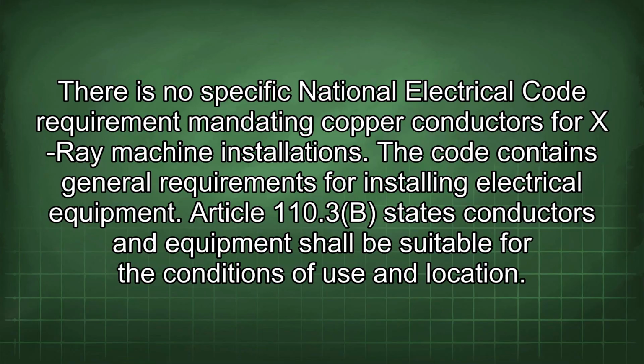There is no specific National Electrical Code requirement mandating copper conductors for X-ray machine installations. The code contains general requirements for installing electrical equipment. Article 110.3(B) states conductors and equipment shall be suitable for the conditions of use and location.